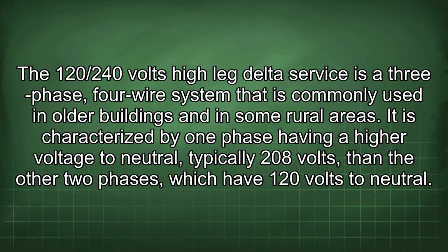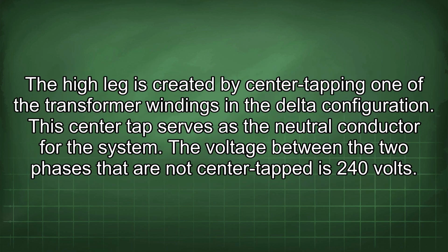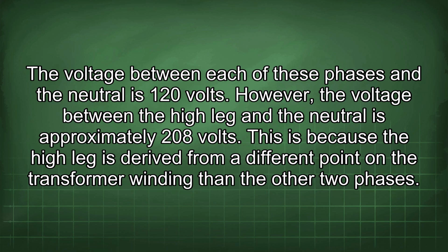The 120/240 volts high leg delta service is a three-phase, four-wire system that is commonly used in older buildings and in some rural areas. It is characterized by one phase having a higher voltage to neutral, typically 208 volts, than the other two phases, which have 120 volts to neutral. The high leg is created by center tapping one of the transformer windings in the delta configuration. This center tap serves as the neutral conductor for the system. The voltage between the two phases that are not center tapped is 240 volts. The voltage between each of these phases and the neutral is 120 volts. However, the voltage between the high leg and the neutral is approximately 208 volts. This is because the high leg is derived from a different point on the transformer winding than the other two phases.